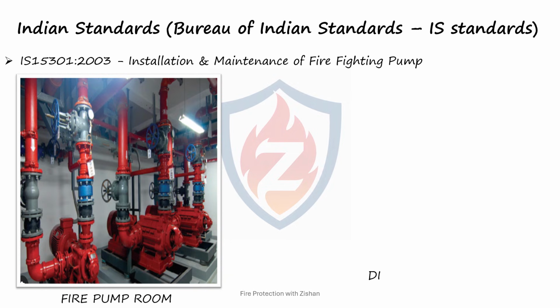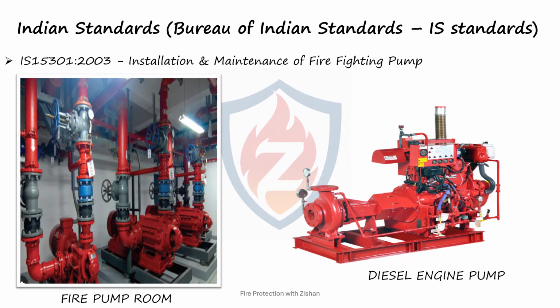On the right, we can see a diesel engine-driven fire pump. Diesel pumps serve as a reliable backup source whenever electrical power is unavailable during an emergency. Since fire incidents can often disrupt power supplies, diesel engine pumps play a crucial role in maintaining uninterrupted firefighting capability. According to IS 15301:2003, fire pumps must be properly installed, regularly inspected, tested, and maintained to ensure their readiness at all times. Periodic testing verifies that the pump can deliver the required pressure and flow whenever a fire emergency occurs.